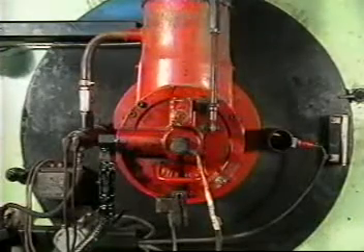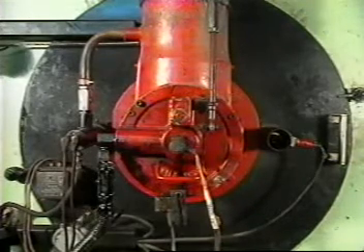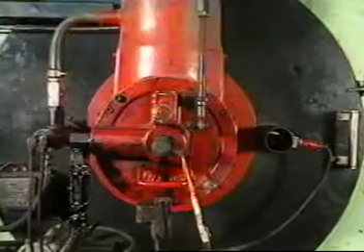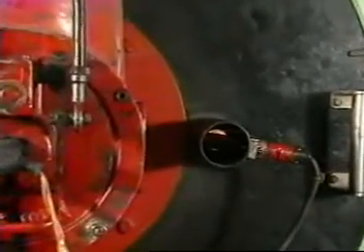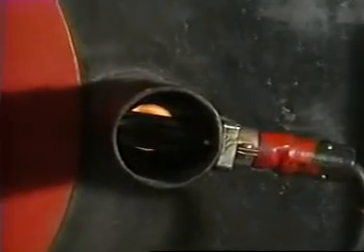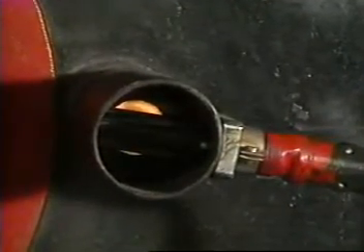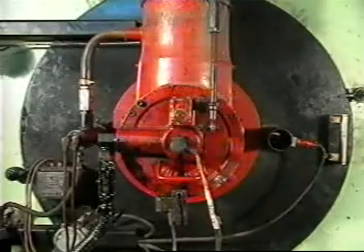Whilst we're dealing with boilers, we must mention a unique sensor and alarm circuit known as the flame-out alarm system. A sudden loss of flame inside the boiler can lead to many undesirable consequences. Therefore, optical sensors, flame eyes, provide continuous monitoring of the presence of flame and will give instant warning should the flame go out.